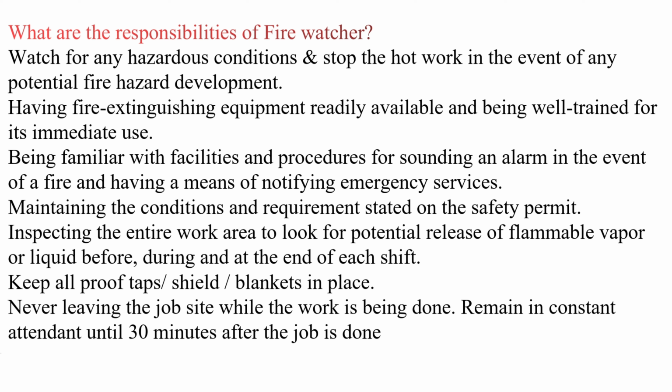Maintaining the conditions and requirements stated on the safety permit. Inspecting the entire work area to look for potential release of flammable vapor or liquid before, during, and at the end of each shift. Keep all proof tarps, shields, and blankets in place. Never leaving the job site while the work is being done. Remain in constant attendance until 30 minutes after the job is done.